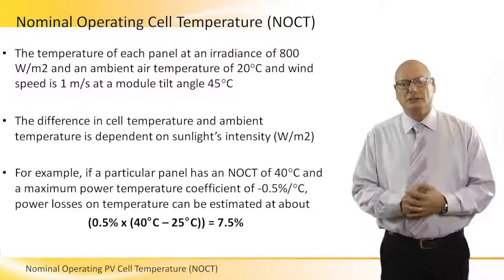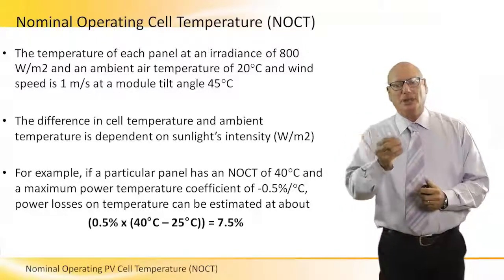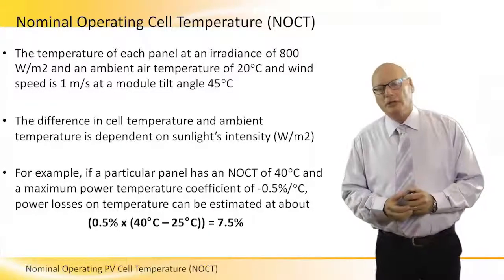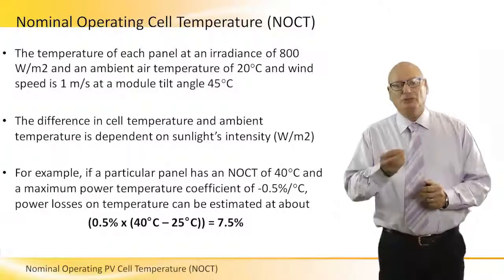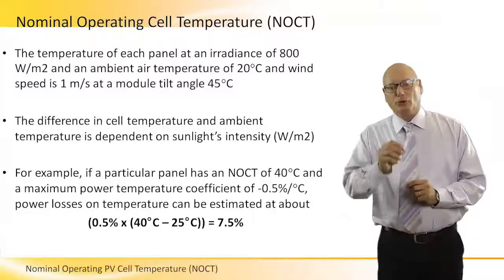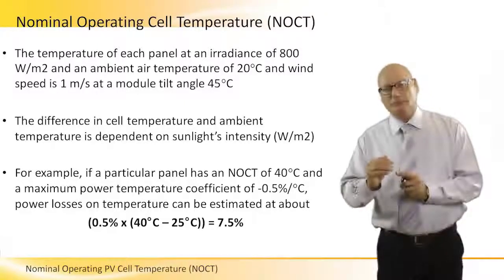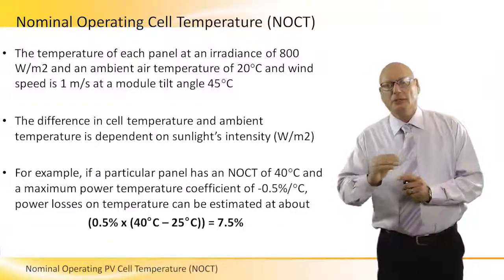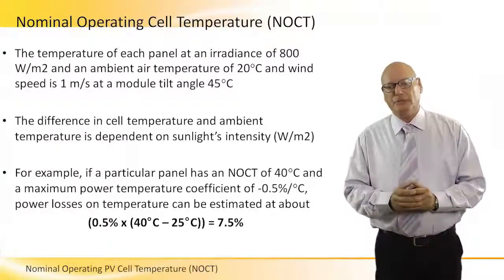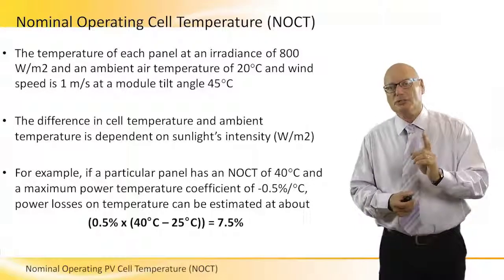Let's take an example. If a particular panel has a NOCT of 40°C and a maximum power temperature coefficient of minus 0.5% per degree centigrade, the power losses due to temperature can be estimated using this formula: 0.5% times the difference between the 25°C reference and the actual temperature. The difference is 15, so 15 times 0.5 gives a 7.5% loss because of temperature.